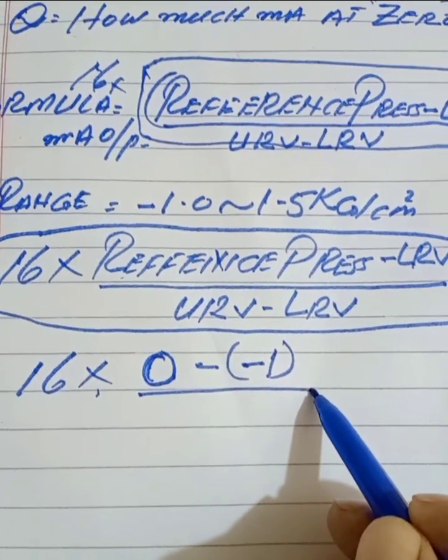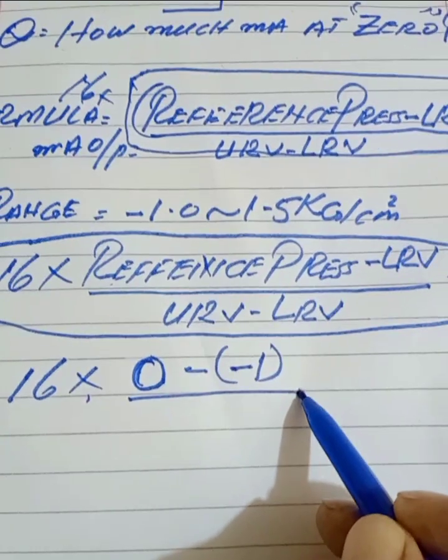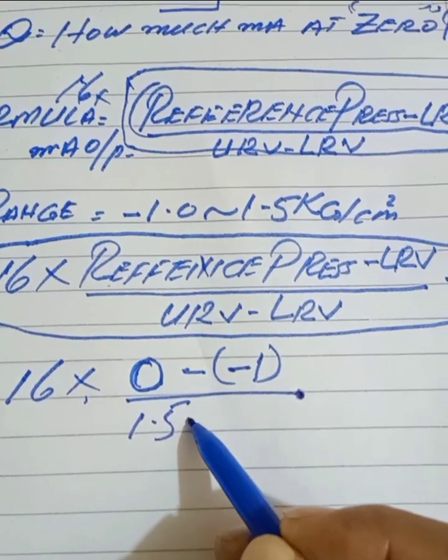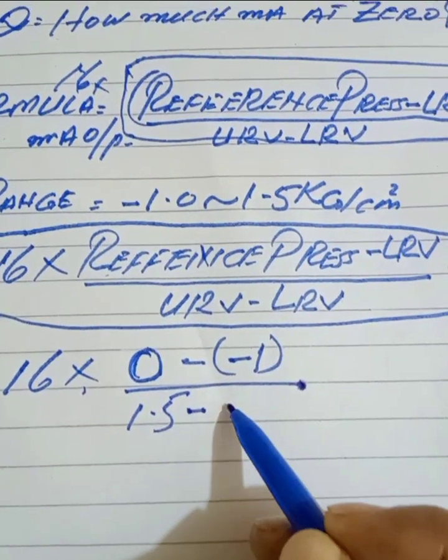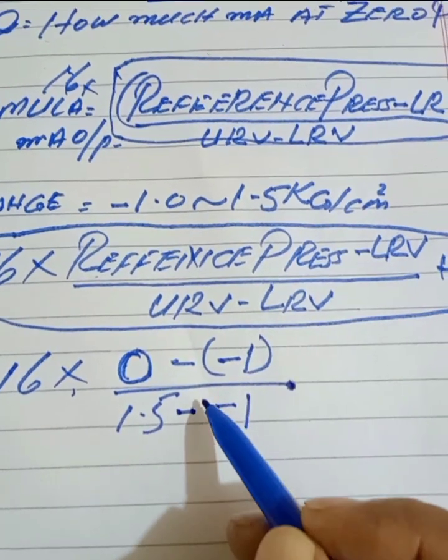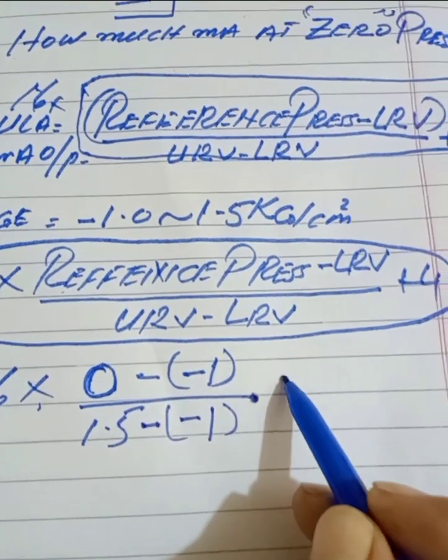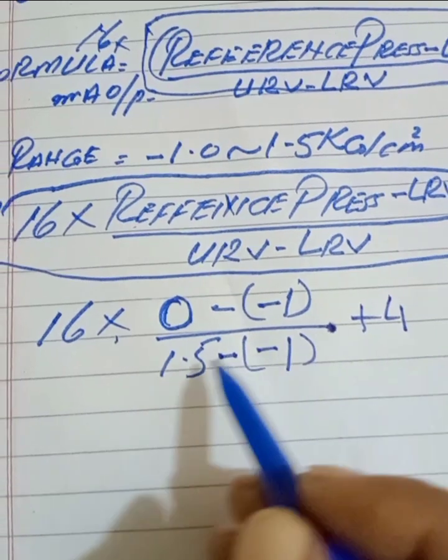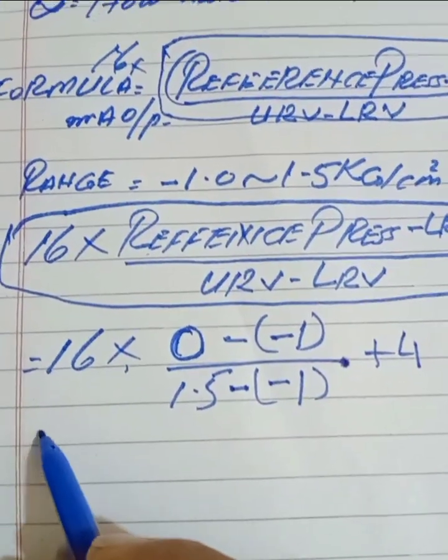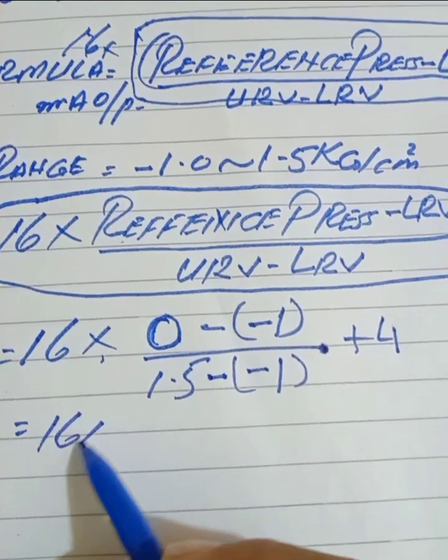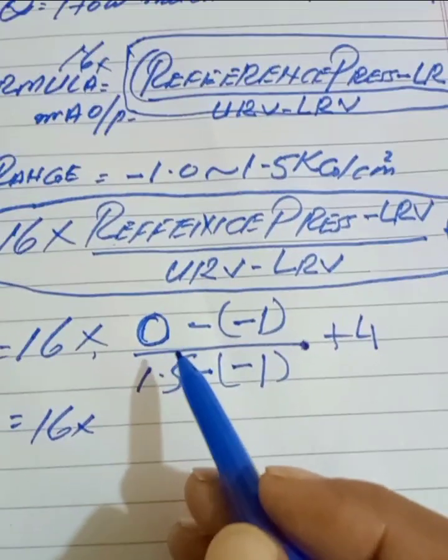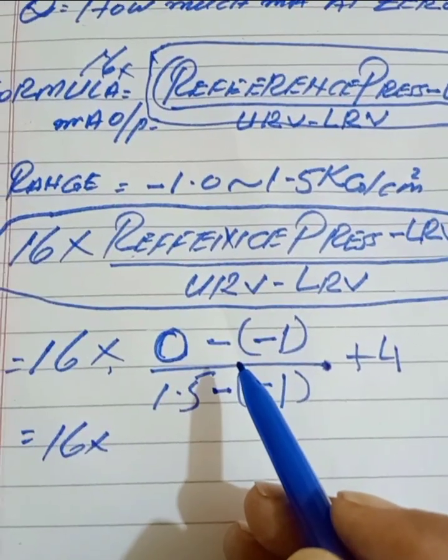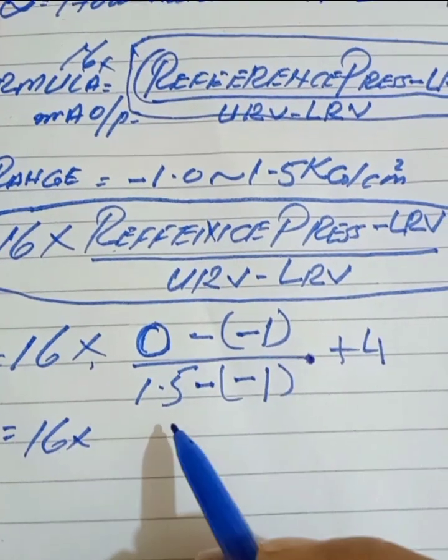Our URV is 1.5. So the calculation becomes: 16 into (zero minus minus 1.0), divided by (1.5 minus minus 1.0), plus 4. Zero minus negative one equals positive one. So the numerator is 1, and the denominator is 1.5 plus 1.0, which equals 2.5.